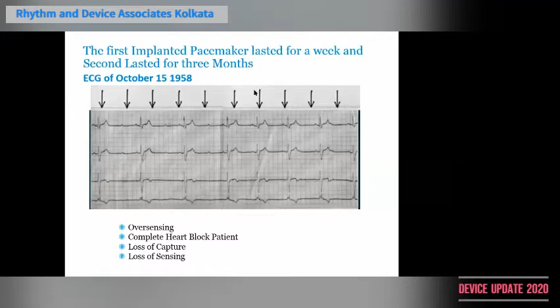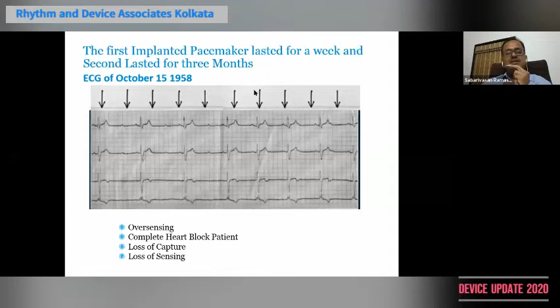But now we find that this particular pacemaker, though it is pacing, has loss of capture. The loss of capture basically means the pulse which is given is not able to depolarize the cardiac myocardium. So basically the programmed energy being given by the pacemaker is less than the threshold, or the stimulation threshold. This is a problem which can happen because the threshold sometimes, for various other reasons, can climb up.